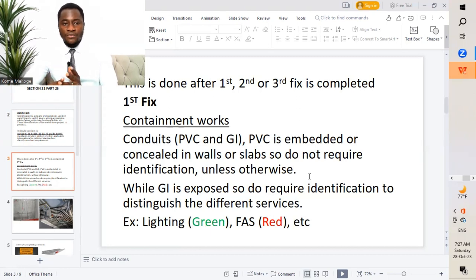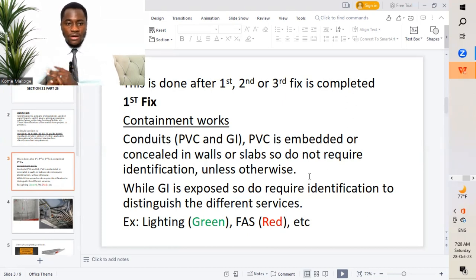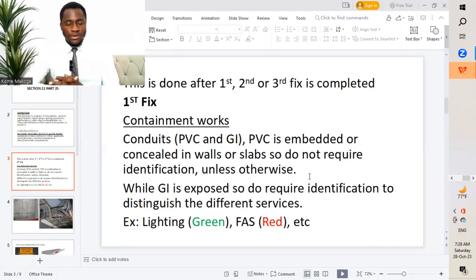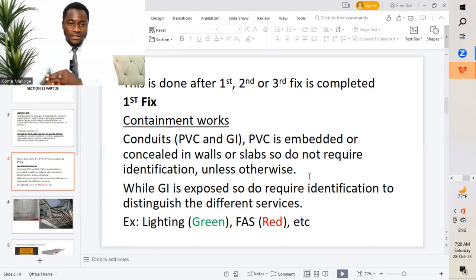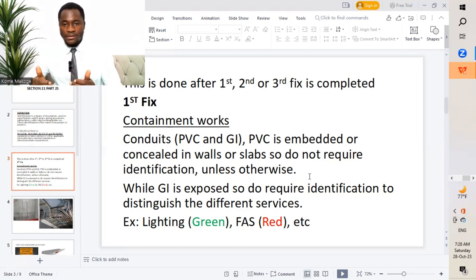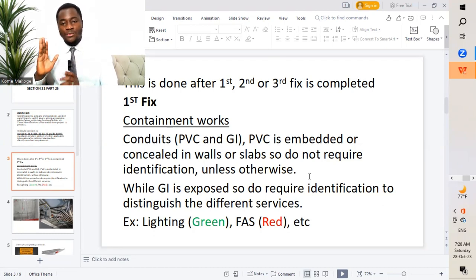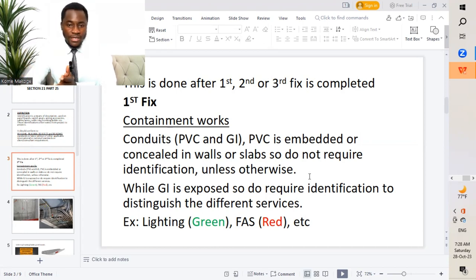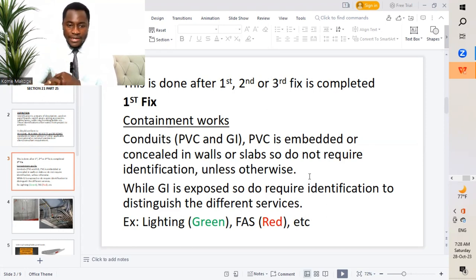This is done after first fix, second fix, or third fix is completed. For first fix, we will be discussing the containment works, which comprises of the skeletal components of that particular installation. This entails conduits — PVC or GI conduits. PVC is embedded and will be concealed in the wall or slab, so it doesn't really require identification unless otherwise — for instance if we're installing on the wall with cladding and the consultant requires identification, then we have to provide it. While GI conduits are exposed, they do require identification to distinguish the different services. So for example, I might use green for lighting, red for fire alarm, etc.